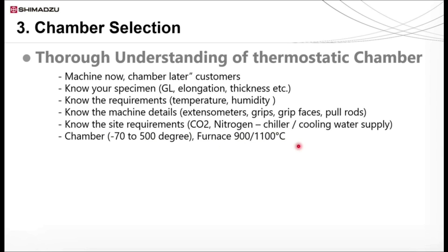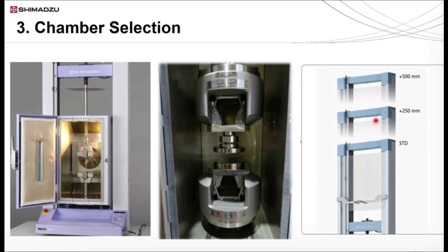Since the grips, extensometer, grip faces, pull rods, etc. are inside the chamber, make sure the temperature specification of all these accessories meets the chamber requirement. Sometimes the grips are too bulky and might not fit inside the chamber. So please make a note of the inner dimensions of the chamber before ordering any special grips from the supplier. An extended length frame model may be required to accommodate the chamber, so check the height requirement of the machine in advance.